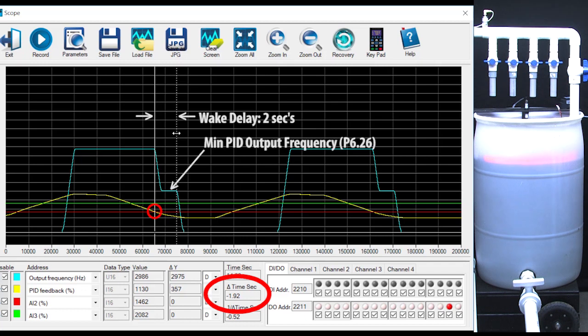you get to specify what frequency you want the motor to hold at while waiting for the sleep delay. Maybe you have a mixing application and you want to mix slowly for a while before shutting down to reduce foaming. Or maybe you have a pumping application and you want the pump to run slowly for a bit to top off the tank with less turbulence before shutting the motor down. Being able to specify that min drive speed during the sleep delay is real handy in those kinds of applications.